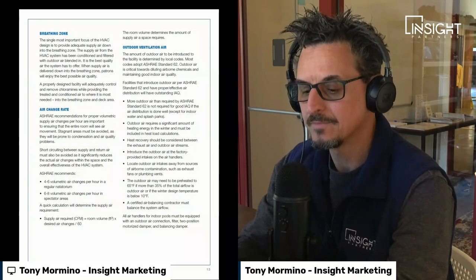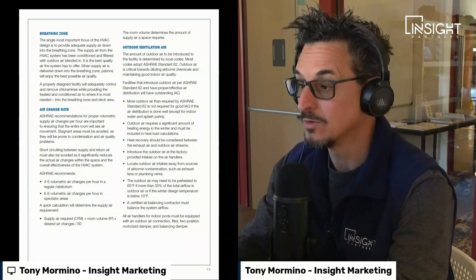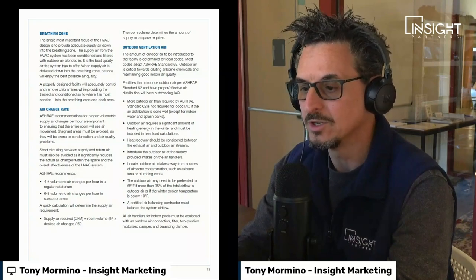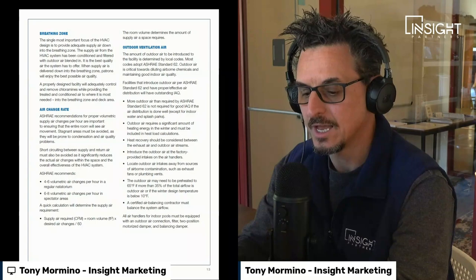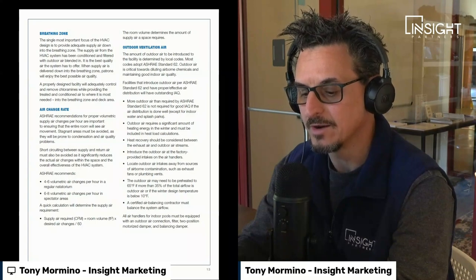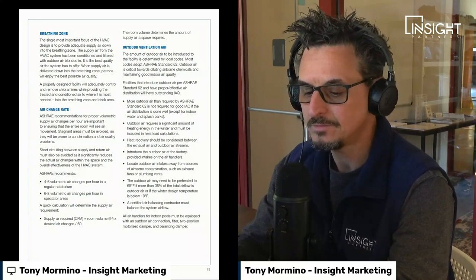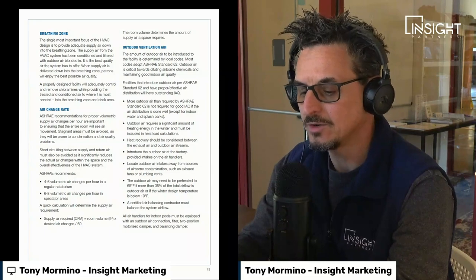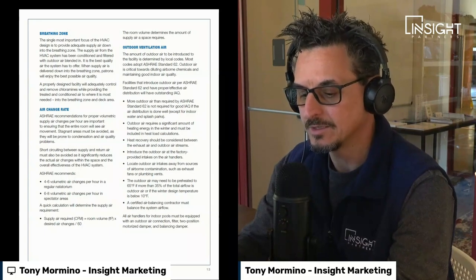On air change rate: ASHRAE recommends proper volumetric supply air changes per hour to ensure the entire room sees air movement. Stagnant areas must be avoided as they will be prone to condensation and air quality problems. Short cycling between supply and return air must also be avoided as it significantly reduces the actual air changes within the space. ASHRAE recommends 4–6 volumetric air changes per hour in a regular natatorium and 6–8 volumetric air changes per hour in spectator areas.